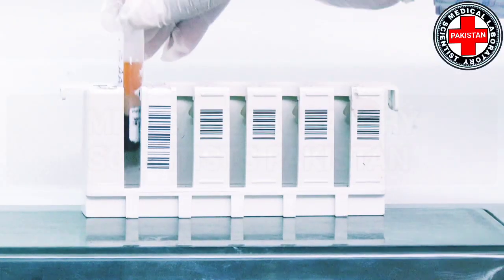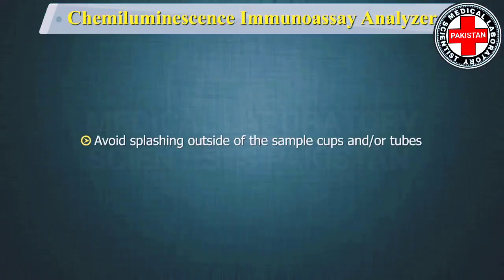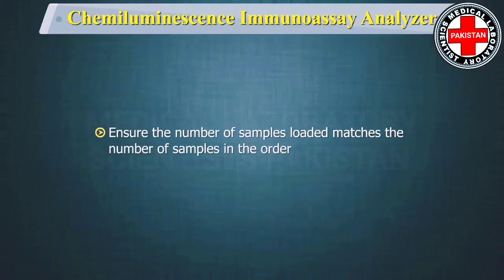You are responsible for loading the correct sample in the correct position. Place the sample in the sample carrier. When loading sample cups or tubes, ensure that you have pushed them completely down into the sample carriers and that they are not tilted. Avoid splashing outside of the sample cups or tubes. Load the carrier into a priority section or a routine section by pushing it in until the indicator illuminates. Ensure the number of samples loaded matches the number of samples in the order.